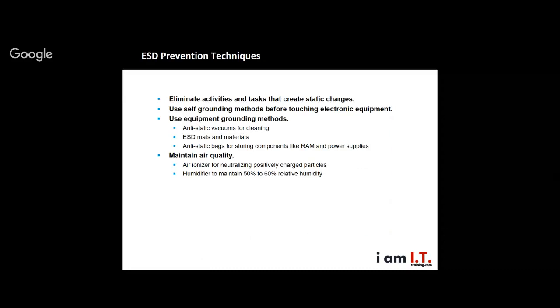Now air quality is actually a pretty big deal here because the humidity in the air can encourage static electricity, bad or good. So if your air is really, really dry, more static is actually likely. The 50 to 60% humidity range is where ESD is going to happen the least. So if you're out in the desert, let's say Arizona or Nevada areas, you have a real issue with ESD and static electricity. So a lot of times they actually humidify the air in their data centers so that this can be decreased.